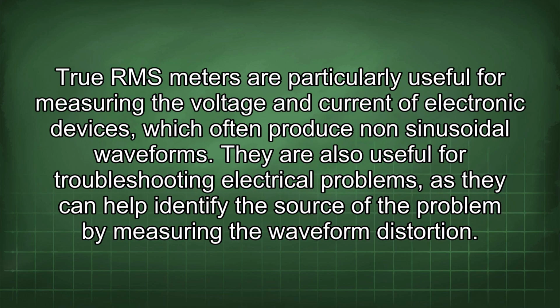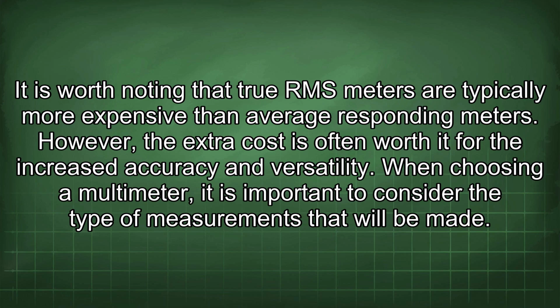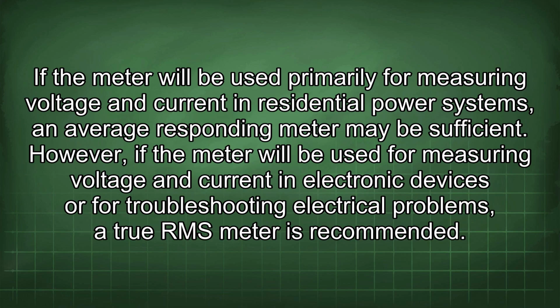True RMS meters are particularly useful for measuring the voltage and current of electronic devices, which often produce non-sinusoidal waveforms. They are also useful for troubleshooting electrical problems, as they can help identify the source of the problem by measuring the waveform distortion. It is worth noting that true RMS meters are typically more expensive than average responding meters. However, the extra cost is often worth it for the increased accuracy and versatility. When choosing a multimeter, it is important to consider the type of measurements that will be made. If the meter will be used primarily for measuring voltage and current in residential power systems, an average responding meter may be sufficient.